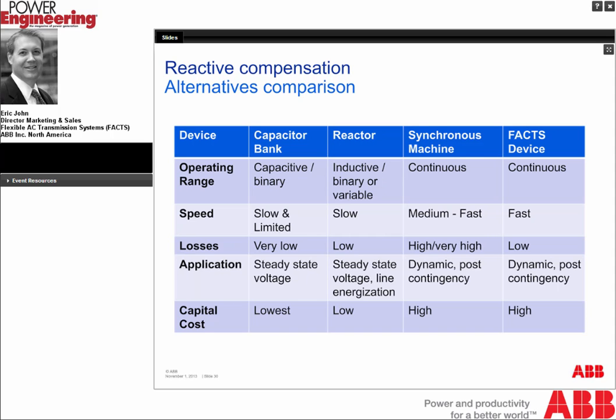And we've included these for completeness because the question always comes up, well, we know that this generator provides reactive support to the system, we'll just install some capacitor banks. And the types of studies that John Daniel just mentioned show very readily that the dynamics are often the most critical aspect to the overall system reliability. And for our purposes of the webinar today, the dynamic devices have a higher capital cost than a static device. And so since they're so important in system reliability and they have a higher cost, we're focused on the more complex technology that's available to maintain grid stability. But this chart is included as a reference for completeness.